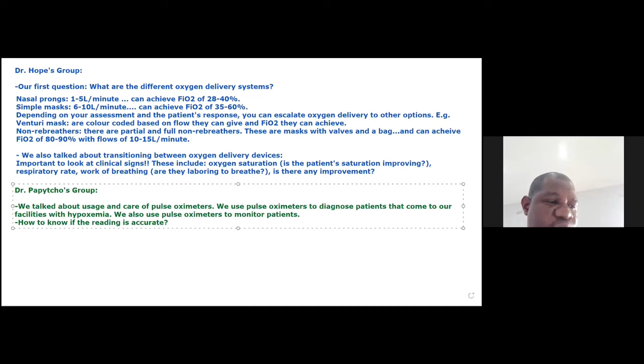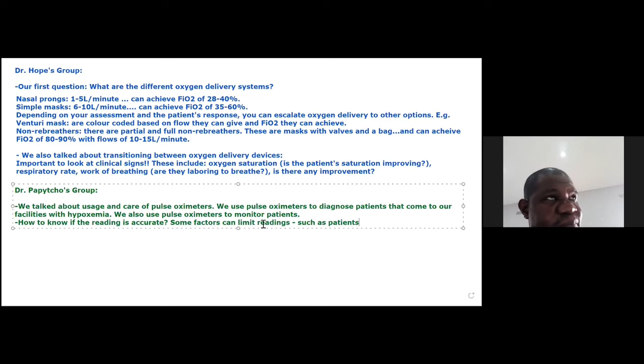We also looked at the limitations in the use of these pulse oximeters. If the patient has nail polish on, it will be difficult for the pulse oximeter to read because it's using infrared to pick the saturations. So there will be that limitation in the picking of the saturations. Secondly, if the patient has very cold extremities, it is also difficult for the pulse oximeter to pick up the saturation. If we have a patient that is constantly moving, like shivering or throwing their fingers about, it also alters the accuracy of the pulse oximeter. And also in patients that are very anemic, it is difficult for the saturations to be picked by these pulse oximeters. So that is all that we discussed in our group.